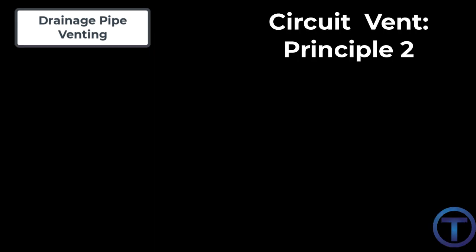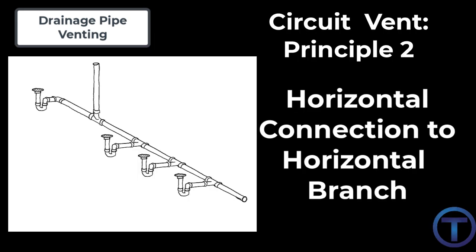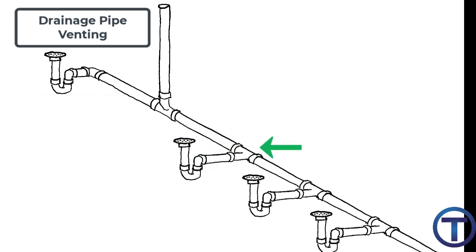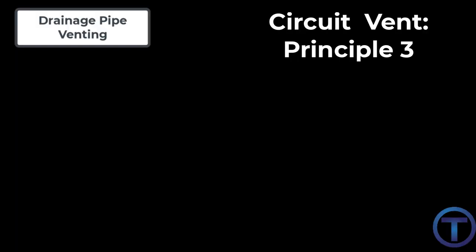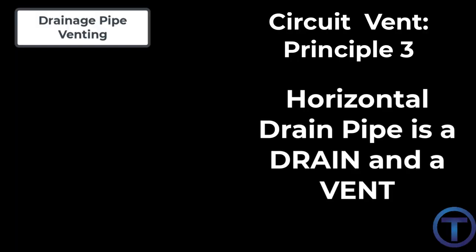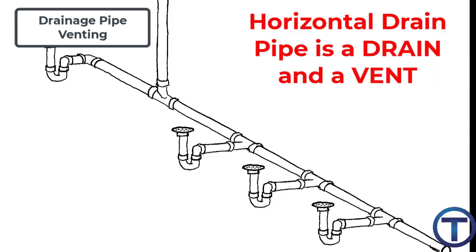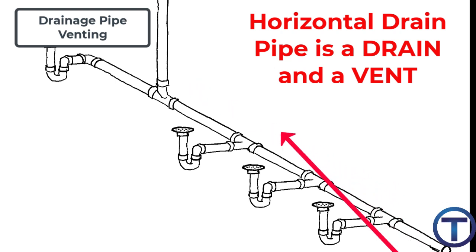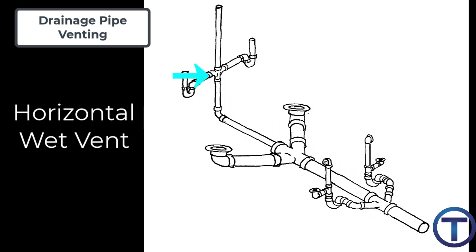Circuit vent principle two: each fixture drain shall connect horizontally to the horizontal branch being circuit vented. Please note this is horizontal connections to a horizontal pipe. Circuit vent principle three: the horizontal drain pipe is considered both a drain and a vent from the circuit vent downstream to the last fixture connection in the circuit. This is a lot like wet venting, where we're using the drain for both a drain and a vent.